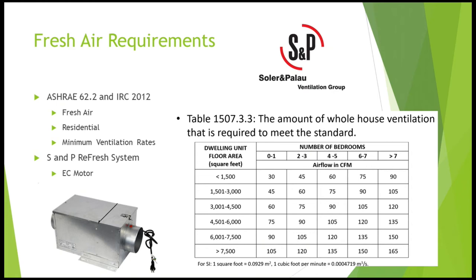In the lower left-hand corner is our refresh kit. It also has EC or DC motors, using DC technology to get an infinite range of speeds. This kit has a filter to clean the dirty air, a fan, and a speed controller you can set in terms of temperature or humidity limits. So if humidity is too high, it'll shut off and only cycle on every 10 minutes to satisfy the fresh air code, without continuously bringing in that extreme air.